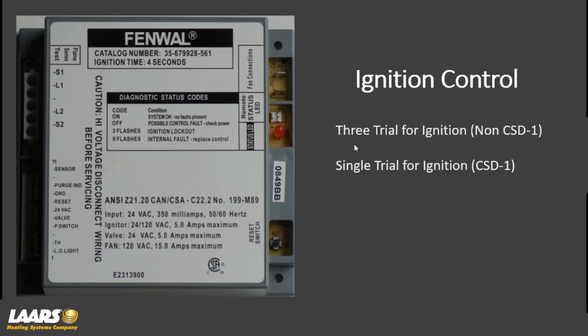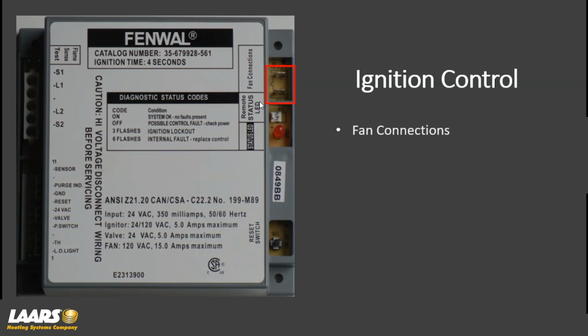Now, a little bit about the control. Non-CSD1 is 3 tries for ignition, okay? So that gives you up to 3 tries. CSD1, and this is all based on the state that you're installing it on. Some states require CSD1 controls. That would be a single try for ignition. Okay? Now, I also want to mention to you that we have fan connections right here.